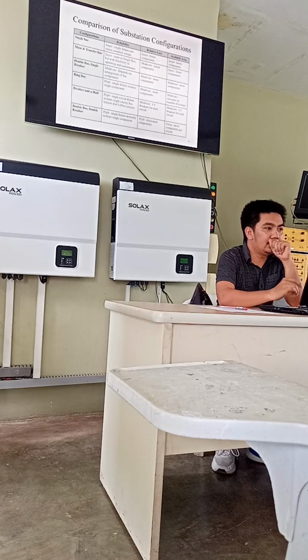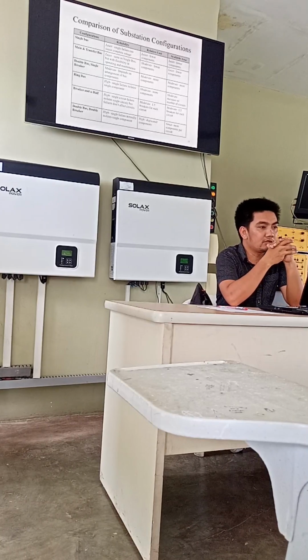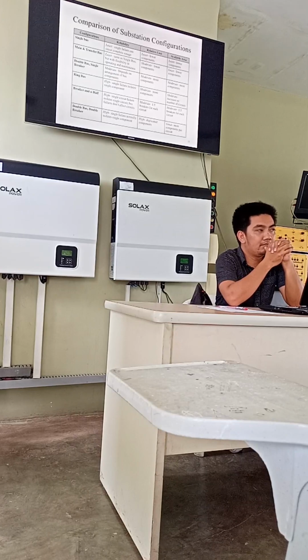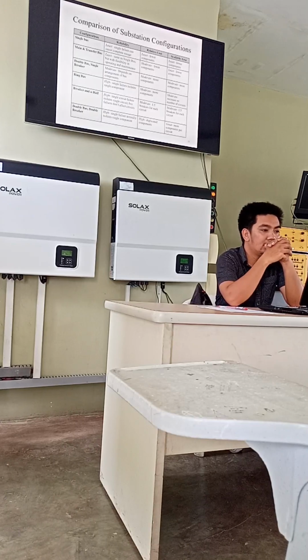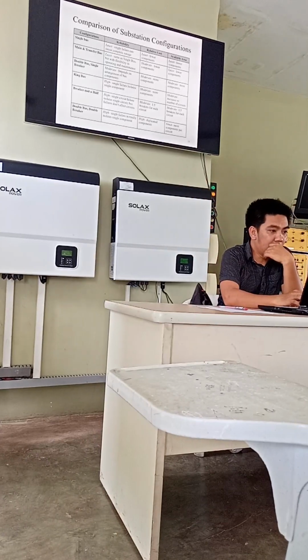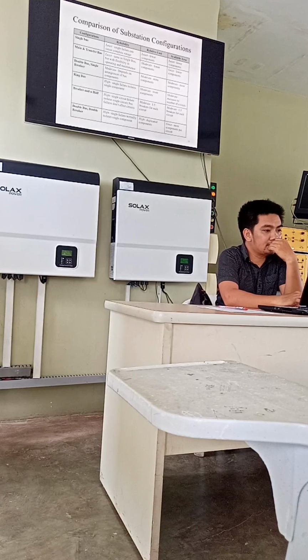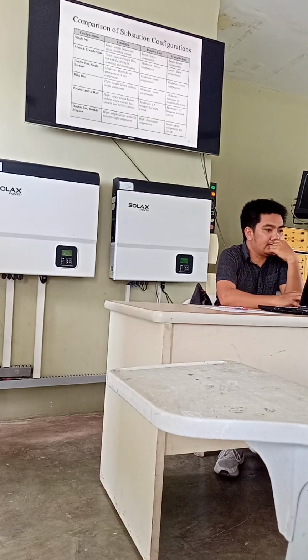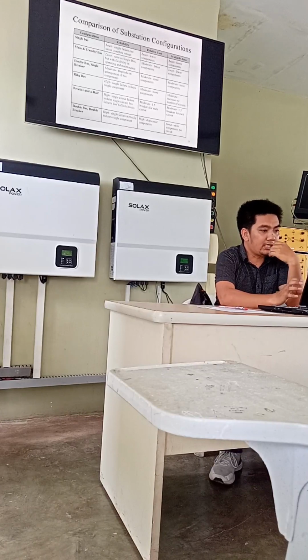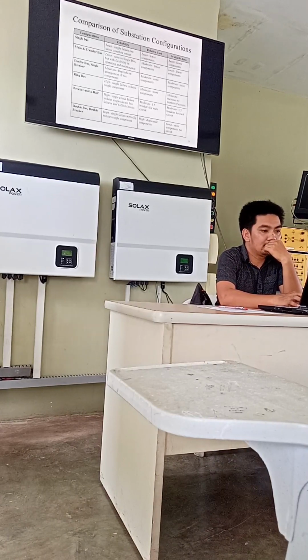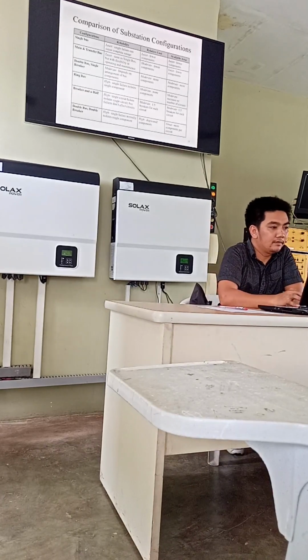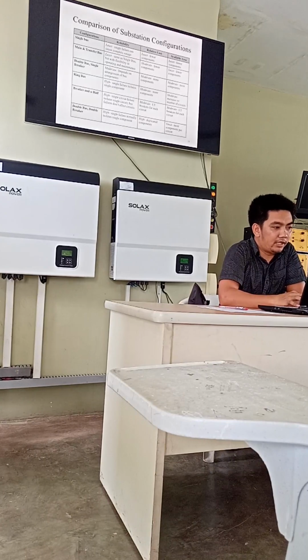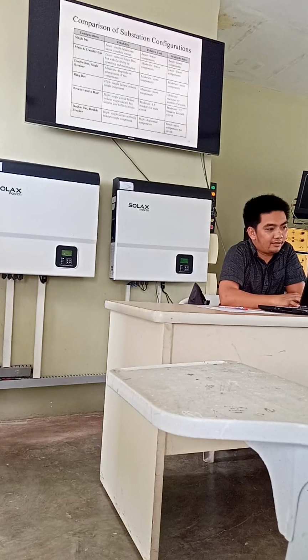In summary, these are the comparisons of the different substation configurations. Single bus provides the least reliability, but it also requires the least cost and least area. On the other side of the table, double bus double breaker provides the highest reliability, but the consequence is it has the highest relative cost because it duplicates the components, and the area required is greater.